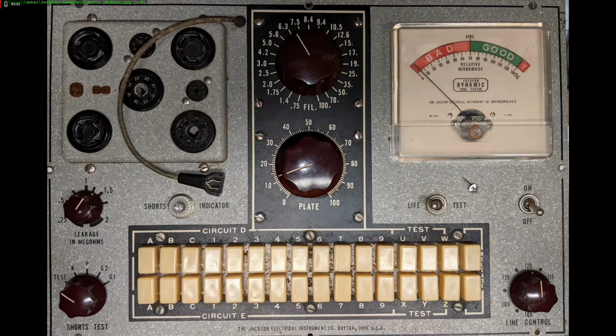But the manual suggests setting the line control with the setting at 100 and then working from there. So if you have a variable supply, that's fine. If not, you can do it at 120 to get the line in the middle. So according to the manual, you'd set it at 100, and we're going to adjust the adjustment on here so that we get the needle right in the middle on the line setting at 100 volts.